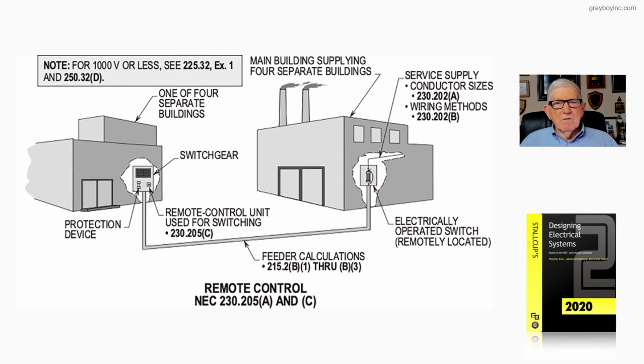As you see in the note at the top left of the illustration, if we're dealing with 1,000 volts or less, we have a similar rule in 225.32 exception 1, along with 250.32D, which requires an isolation connection of the equipment ground and neutral in accordance with 408.40 of the code.